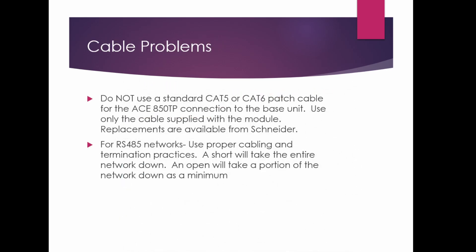Don't use a standard Cat5 or Cat6 patch cable for the ACE850TP connection to the base unit — use only the cables supplied with the module. Replacements are available from Schneider, and longer ones can be special ordered. For your RS-485 networks, use proper cabling and termination practices. I've seen things just twisted together with wire nuts and grounds left off. Make sure your terminations are neat — a short will take the entire network down, and an open can take everything downstream offline or even the whole network.